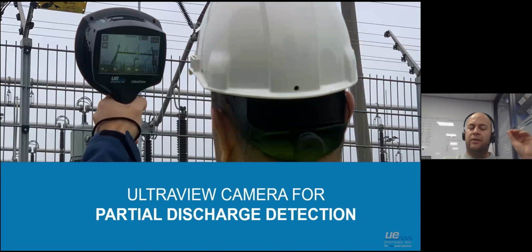Okay, so that was the leak detection part. What we have here, you also see me inspecting outside the fence on high voltage systems, high voltage power lines. You can inspect high voltage and medium voltage with the UltraView camera. The nice thing about this camera is it will tell you what kind of discharge it is, so you don't have to do extra analysis or diagnosis with external software. Eventually, when the snapshots go into the cloud, it will tell you what kind of discharge it is.